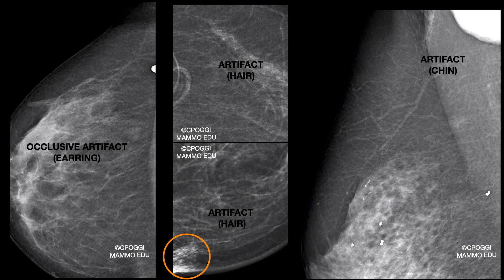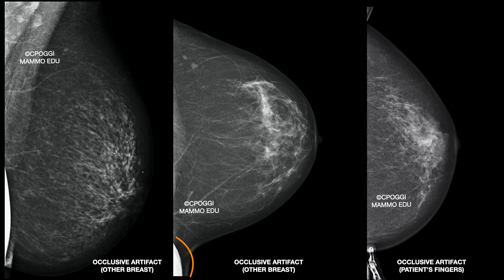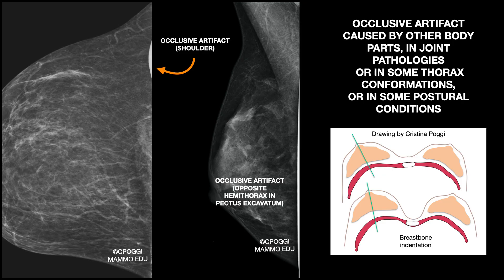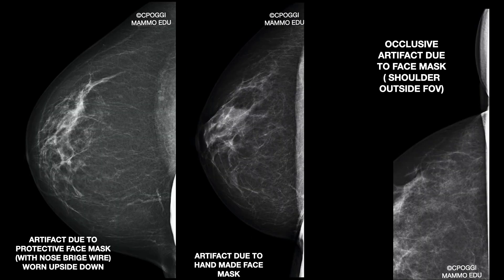Occlusive artifacts result from objects or body parts projecting themselves onto the breast: earrings, hair, chin. We have to check carefully for any shadow projecting onto the field of view. It could be the other breast too, which should be kept away by the patient herself — or even the patient's finger. Some occlusive artifacts are correlated to patient joint pathologies or, in a healthy patient, to their thoracic conformation — for example, an artifact due to the opposite hemithorax in a case of pectus excavatum. We also have a brand new artifact in mammography due to a face protection mask worn upside down with the nose bridge wire on the chin.